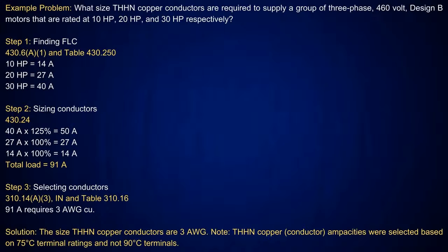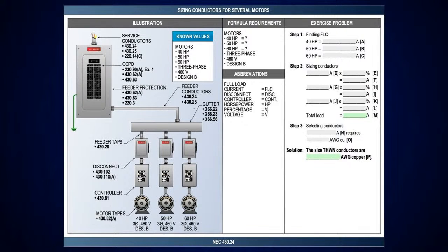Then I'm going to go down to step 2, and if I look at 430.24, the largest motor is taken at 125%, all the rest are added at 100%. So 40 amps times 125% is 50 amps, then add the 27 amp and the 14 amp motors, and that gives you 91 amps. Go to table 310.16. The next size above that in the 75-degree C column is 100 amps, which requires a number 3 conductor. Now, was that hard? No, and it brings up one question that I want to ask though.